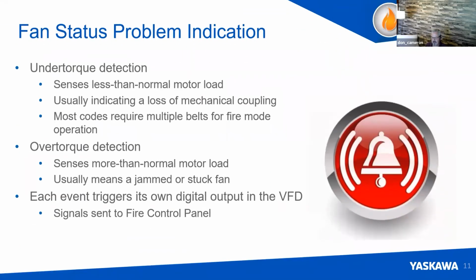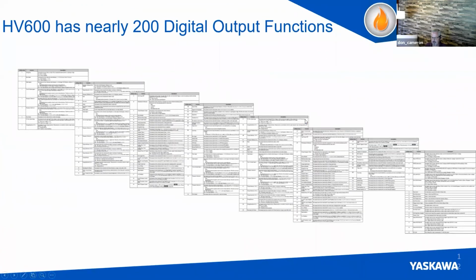So under torque detection, again, it senses that the load is less than normal. Over torque, it's a jam situation. And these can both be sent back to the alarm control panel for signaling. And there's practically, I think it's 180 something, but there's probably combinations within that make it even more. You can have 200 different digital output functions from the HV600. So I know I'm beating this into the ground, but whatever it is you're trying to do logic-wise at that job site to satisfy the code requirements, the HV600 can do it, assuming that the installation is set up to achieve what you're trying to do.